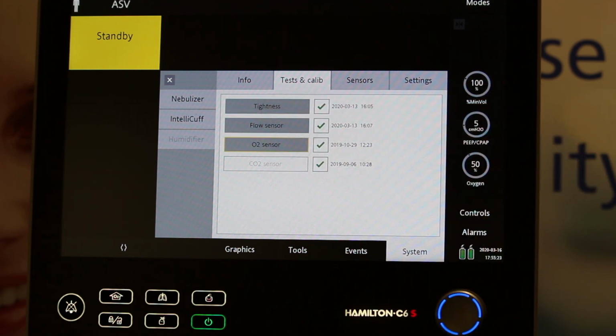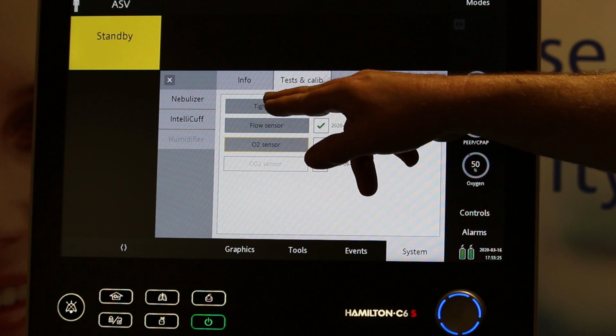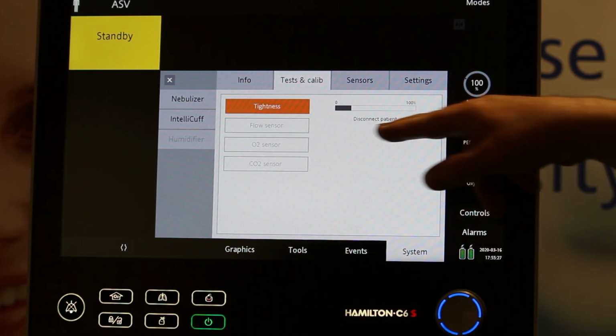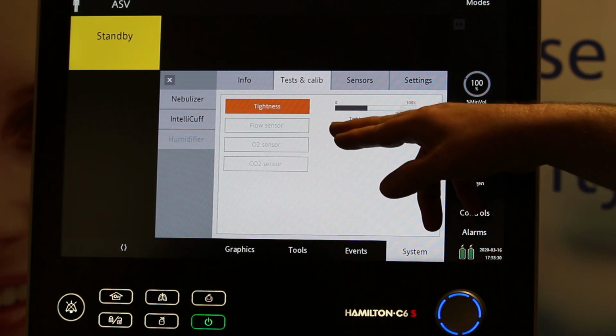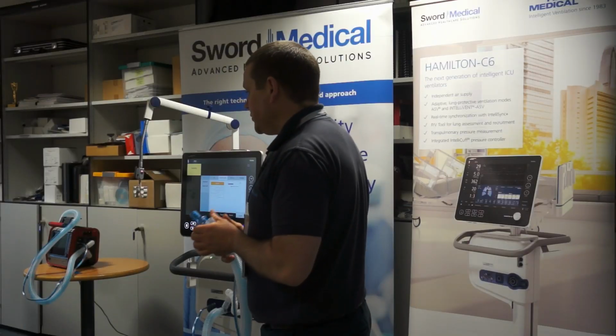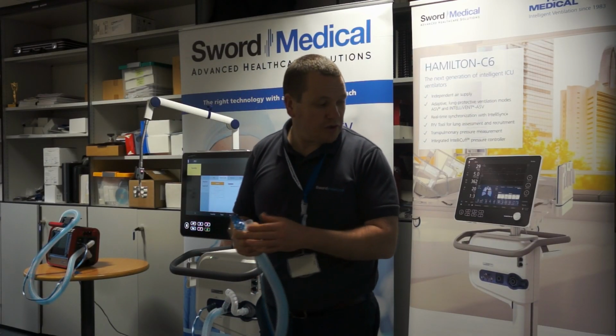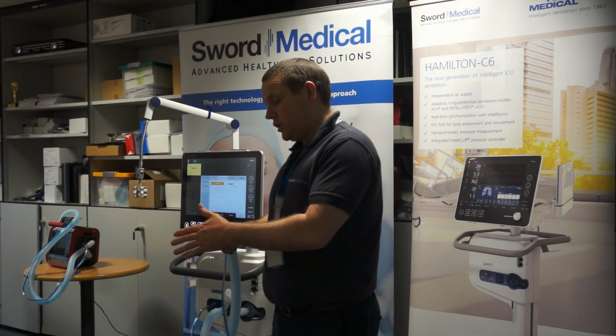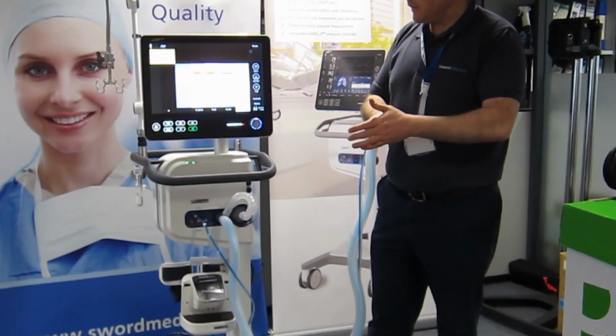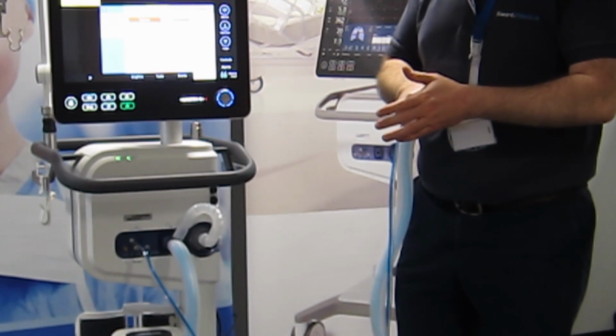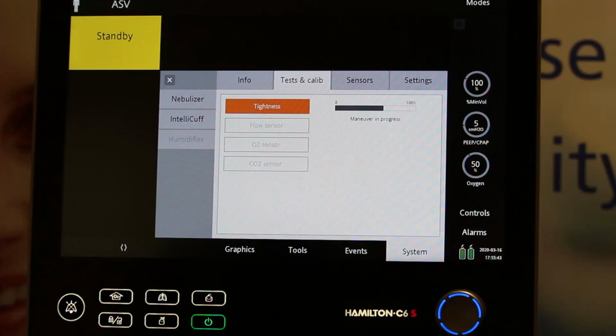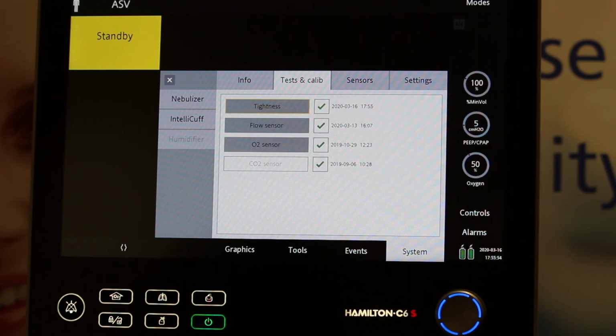So the next test I'm going to do is tightness. Here I hit tightness, the ventilator tells me to disconnect the patient, and then it prompts me to test the tightness of the system. Using a gloved hand, or putting the dust cover of the circuit back on, occlude the end of the circuit. You'll hear now the ventilator ramp up the pressure within the circuit. It's looking for a leak anywhere along it. And that's it. So then hopefully we get the green tick and the date and the time.